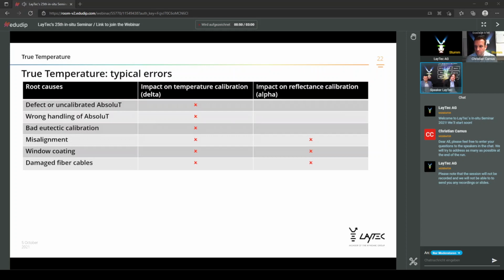That does not mean that the fiber cables are as fragile as a raw egg or thin glass; they are quite robust. But on the other hand, you have to maintain them and treat them well in order not to damage the inner fiber core. Keep in mind that the inner core has a diameter of 600 micrometers and only allows a minimum bending radius. Any radius smaller than the minimum allowed bending radius bears a very high risk of damaging or cracking the inner fiber core.